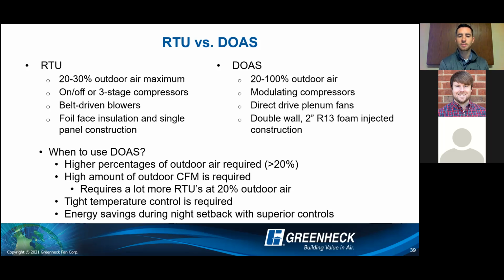And it's really due to the superior controls and modulating compressors, things like that, where during night setback, we still want to maintain that temperature and humidity in the space. We don't want sick building syndrome. We don't want it to go unconditioned during those setback hours. So what we do is, with our control strategy, we can still have different unoccupied set points that might be a little bit higher from a temperature and humidity standpoint, but we'll read those and we'll control our compressors and our heating the same way. We'll stage our fans on just to move enough air to get that back down to set point, which means we're saving energy in the long run. So those are the general themes when you're going to want to look at that RTU versus that DOAS, and make that jump over to the RVE product line.